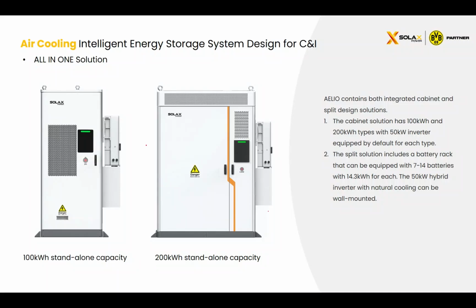Okay, so let's talk about the cooling method for the AELIO first. There are 2 main cooling methods for commercial and industrial storage systems on the market: one is air cooling and the other is liquid cooling. For the AELIO, it only uses the air cooling system, meaning the AELIO has an air conditioner on the front side of the cabinet, like this. The air conditioner ensures that the system will always work at a suitable temperature, avoiding system failures or system loss due to too cold or too hot temperatures.